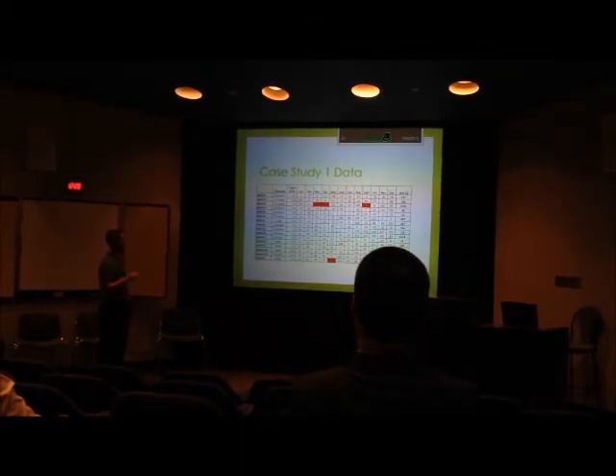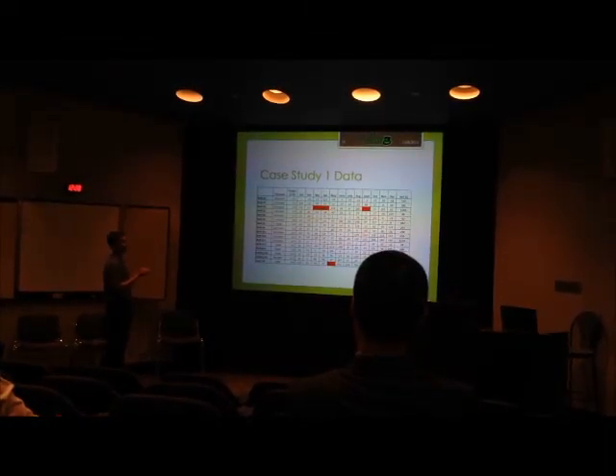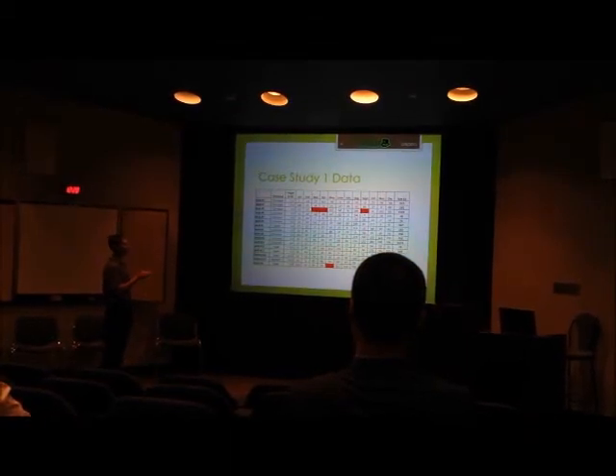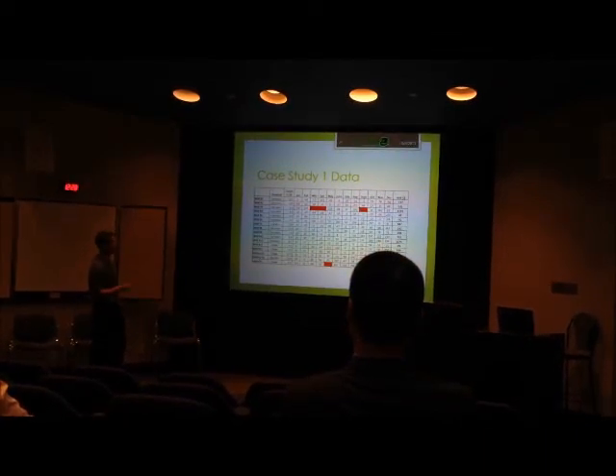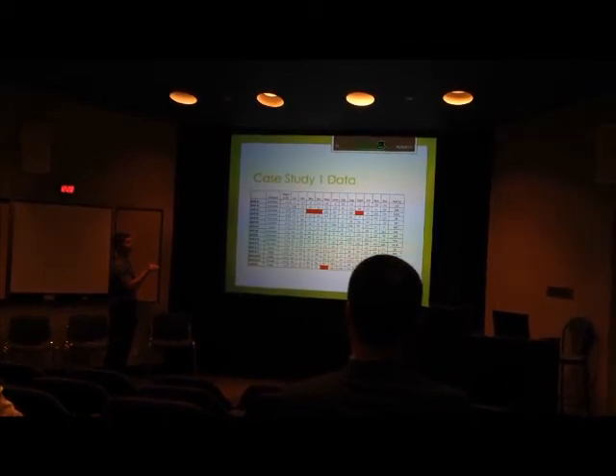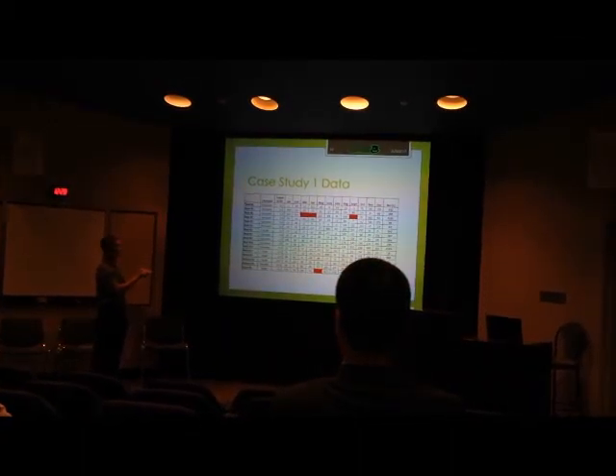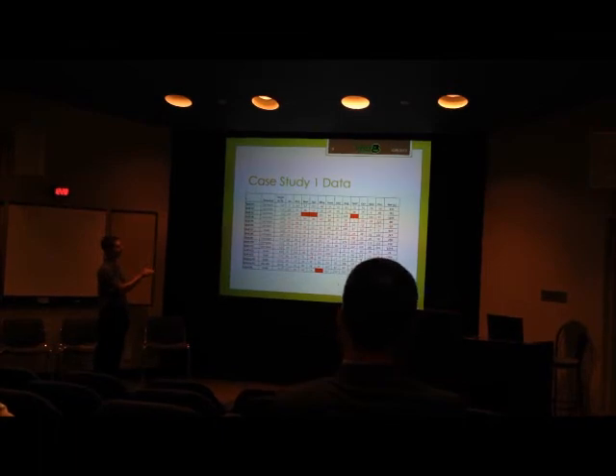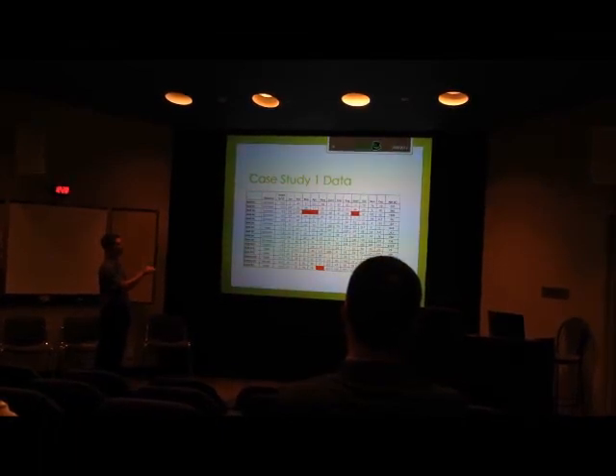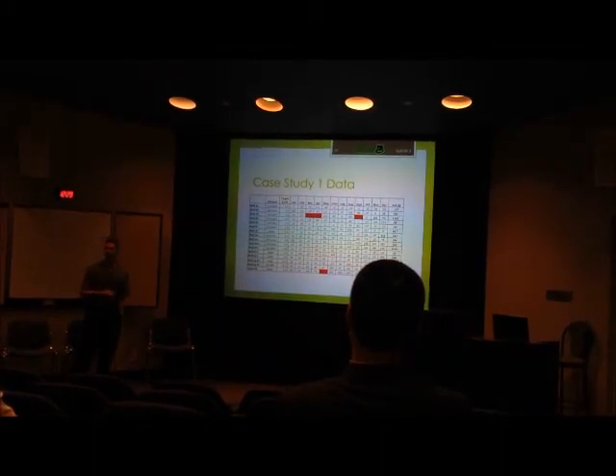So here's a case study we did for this company here. January, they only pumped 2 liters over their target rate for the whole month. Pretty good, they were right on, or their pump was down for a while. Next month they were 47 under, 17 over, 112 over, 49 under, 9. I see this quite a bit when we do case studies. So pump was probably down, maybe down again, gets it going, really gets it fixed good, gets in trouble for over-injecting, trims it back, gets too lean, stalls out, too lean again, gets in trouble, hits it, cranks it up, over-injection, well, it has to trim it back down. So it's just a cycle like that trying to achieve those rates because these rates are really hard to achieve.